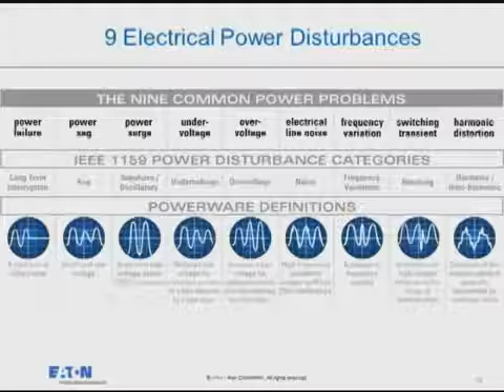It's also invisible, right? I can't tell you if there's electrical line noise. I can't tell you what the harmonic distortion is in this building at that receptacle. Now, I can take a meter, and I can go there, and I can meter it, and I can tell you, okay, at this instant, it's pretty good. Pull it out, I can't tell you what it is anymore because it could happen or not happen. But the loads are susceptible to this information. The loads will see it.